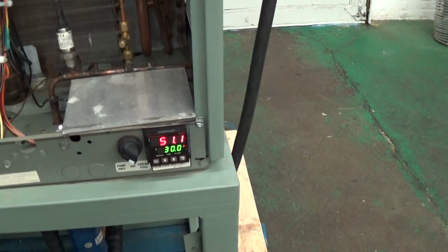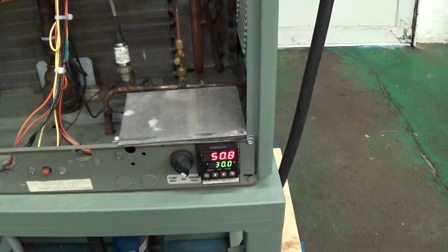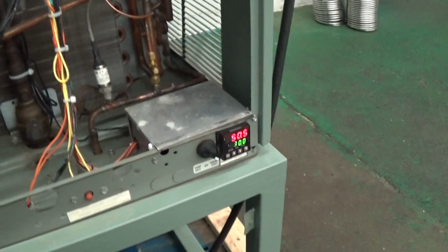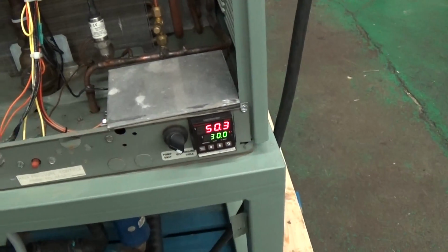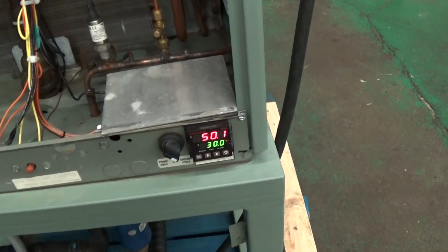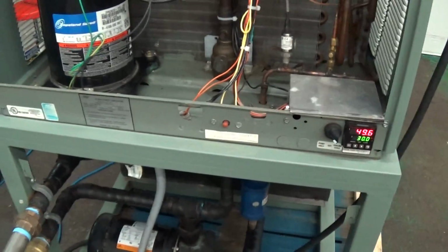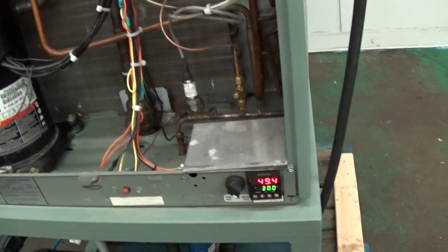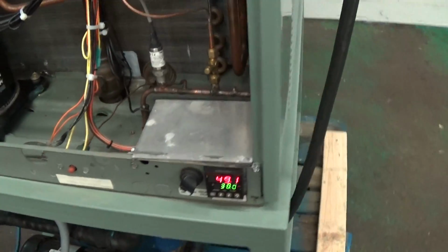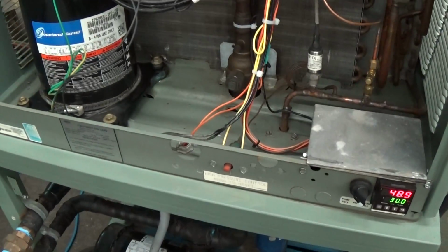So you can see we're already down to 51 degrees, and this will overshoot a little bit, several degrees or a few degrees past that set point, just because of the inherent refrigeration and the low load and the relatively low amount of fluid that's in the tank right now.